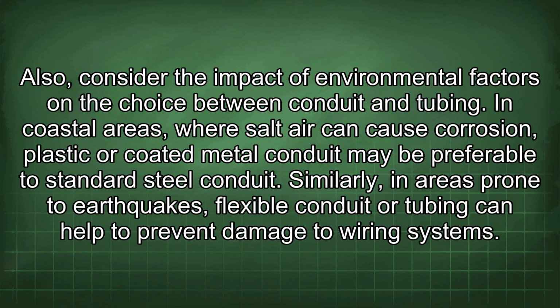Also, consider the impact of environmental factors on the choice between conduit and tubing. In coastal areas, where salt air can cause corrosion, plastic or coated metal conduit may be preferable to standard steel conduit. Similarly, in areas prone to earthquakes, flexible conduit or tubing can help to prevent damage to wiring systems.